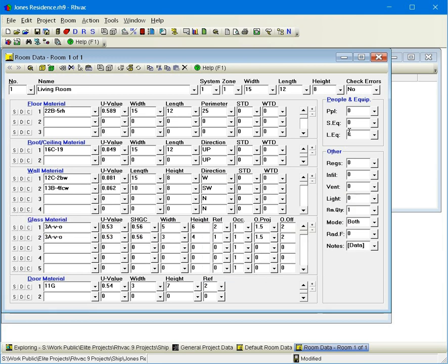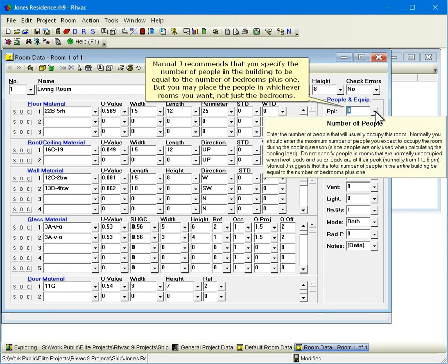Manual J recommends that you specify the number of people in the building to be equal to the number of bedrooms plus one, but you may place the people in whichever rooms you want, not just the bedrooms.